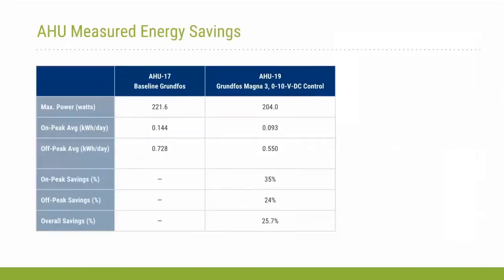So this shows the measured energy savings from the two. I think it's important to note, if you look at the first line, the max power is just slightly lower for the high performance circulator pump. If you remember on the domestic hot water ones we went over, we saw somewhere from 44 to 73% reductions in peak power when we compared this to an older pump. When you're comparing it to a new market standard pump, it's very little energy savings at peak power. I think it's only about 7%.